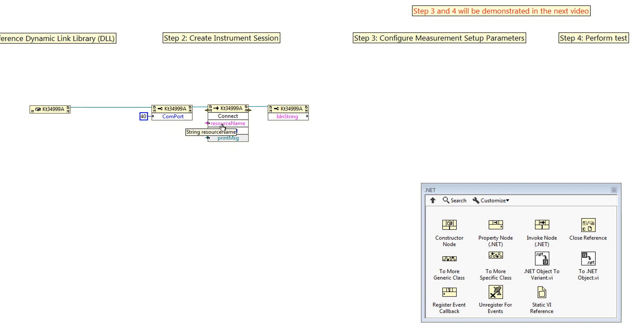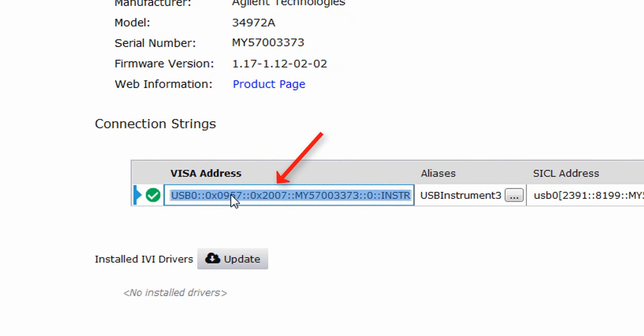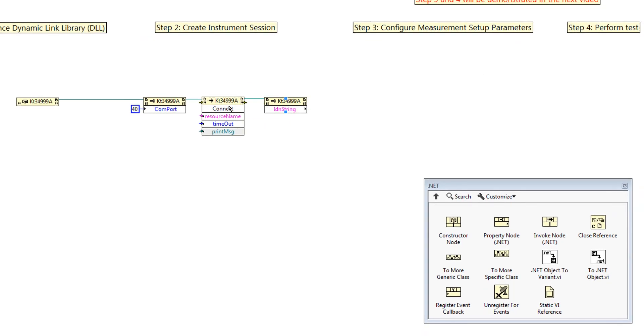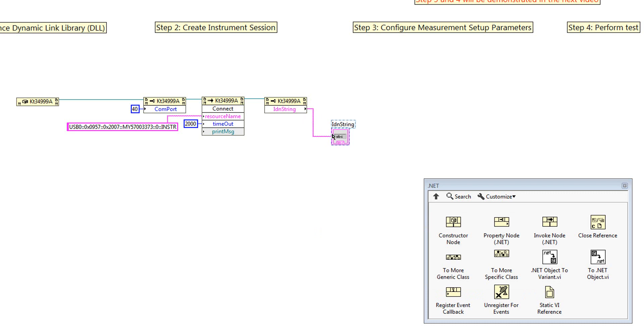Next, we need to input the resource name. The resource name refers to the VISA address. Go to Connection Expert, find our VISA address, and copy it. We create a constant and paste it in. Next, we create another constant for the timeout. The timeout here is in milliseconds, so we input about 2000 milliseconds, which is two seconds. For the IDN string, we create an indicator. In this case, we read the IDN from the driver and it will display at the IDN indicator.